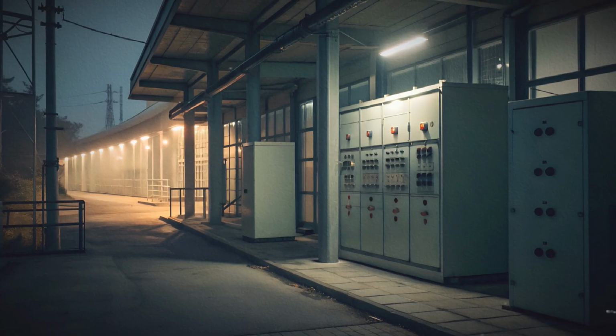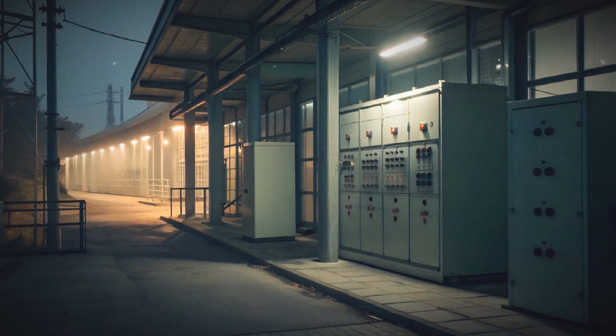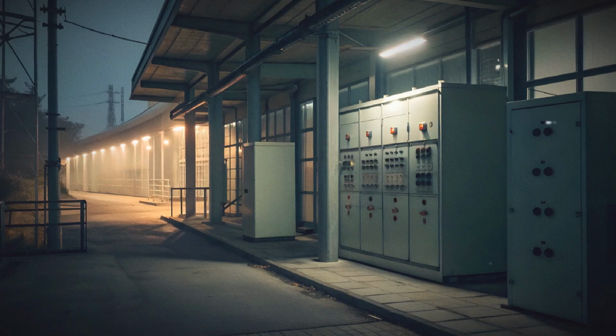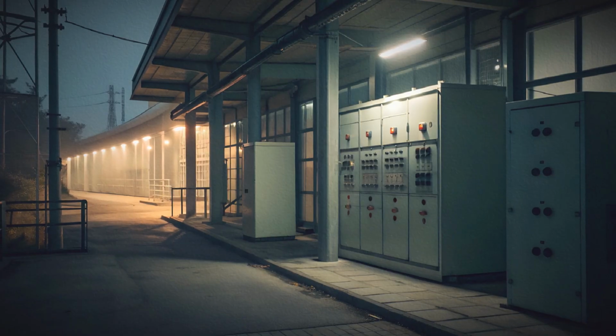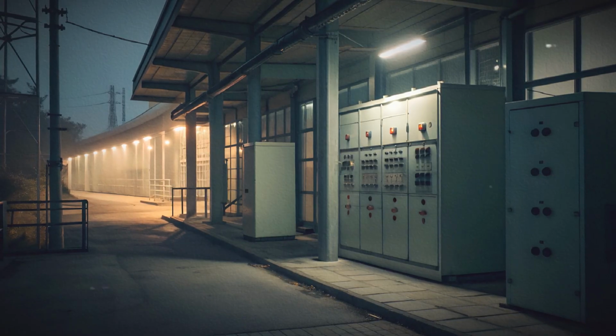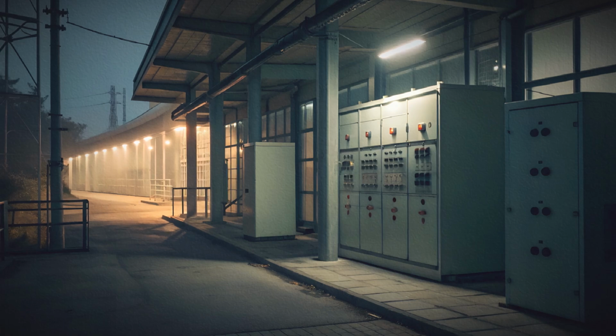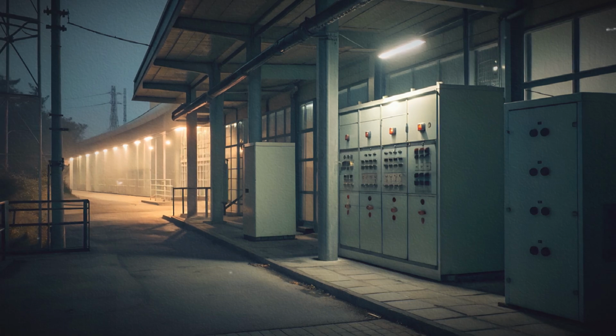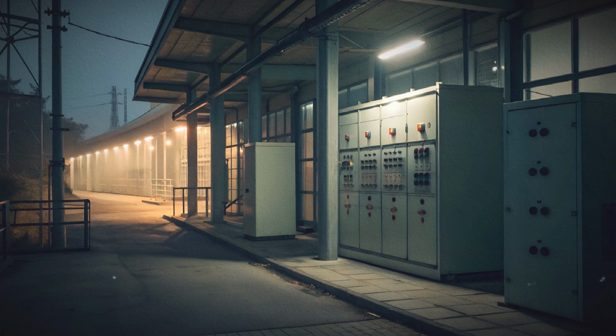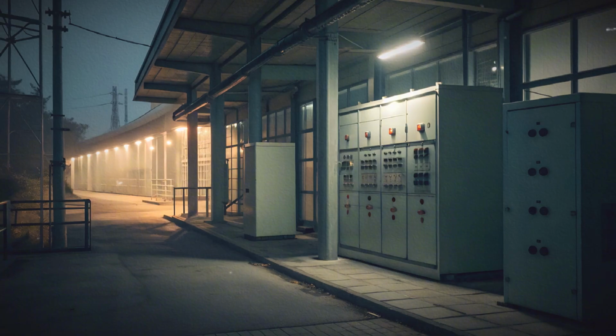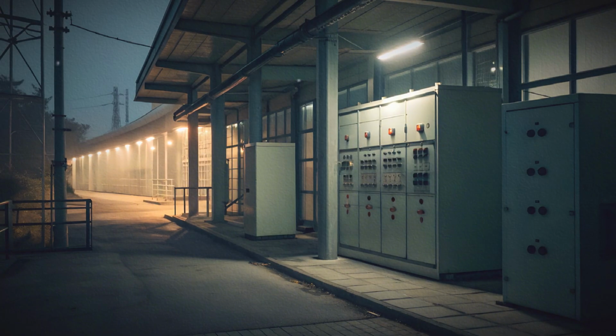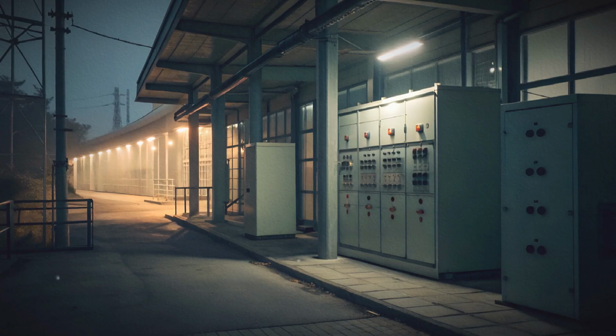Circuit breakers carry out the physical action of opening and interrupting current flow. They are rated for high voltages and are designed to extinguish the electrical arc that forms when a circuit is opened under load. Breakers open when instructed by relays. They can also reclose automatically in some applications, which is useful for clearing temporary faults.